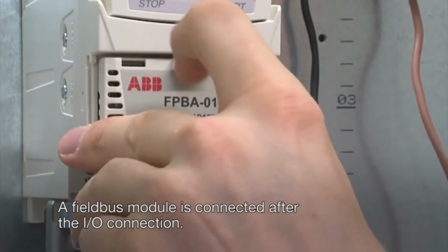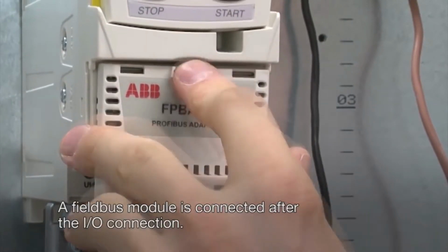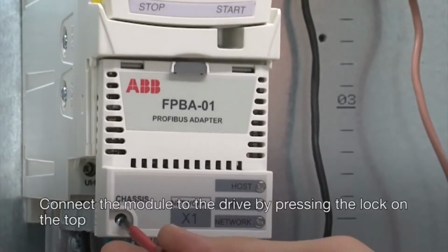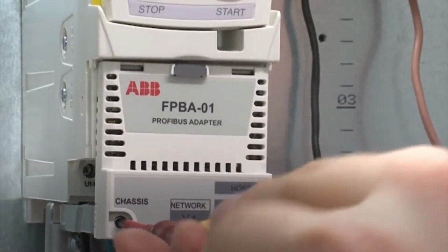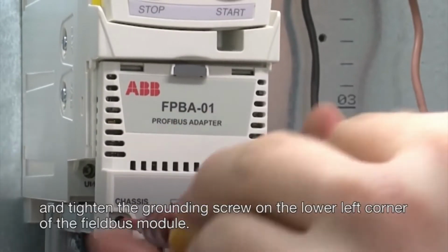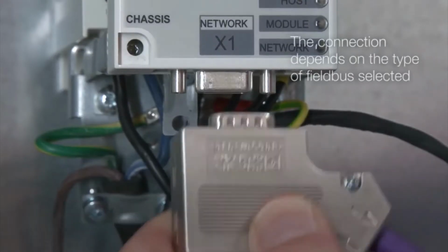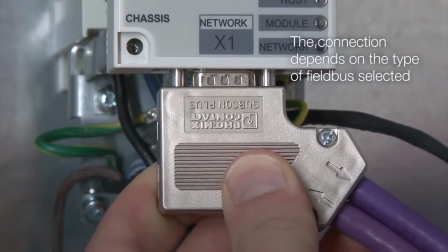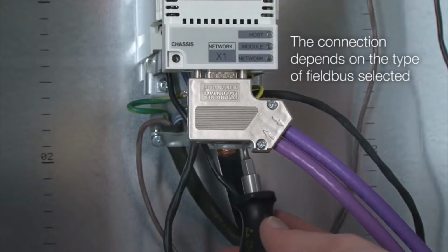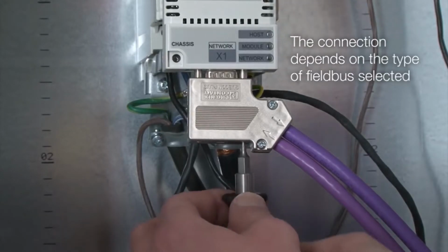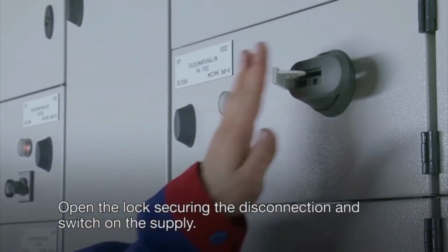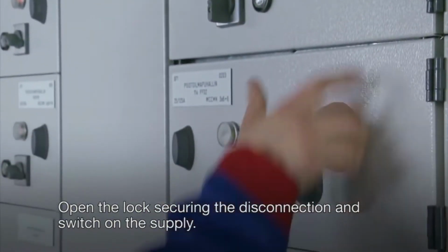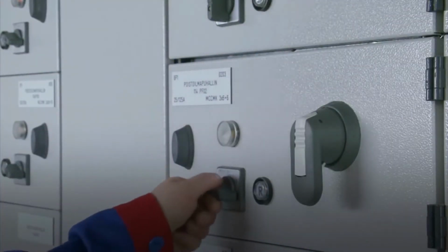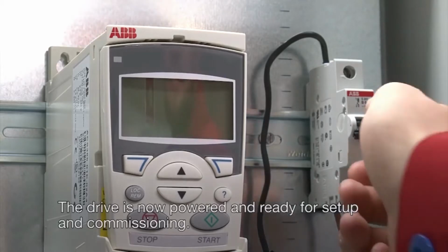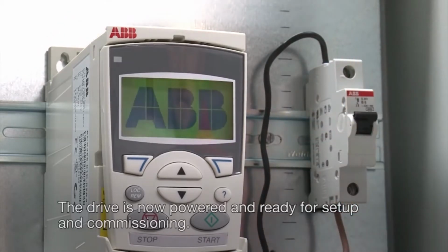A field bus module is connected after the I/O connection. Connect the module to the drive by pressing the lock on the top and tighten the grounding screw on the lower left corner of the field bus module. Open the lock securing the disconnection and switch on the supply. The drive is now powered and ready for setup and commissioning.